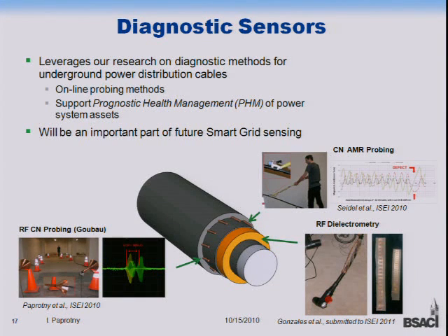The idea is that we can have a sensor that measures the flow of power through the system, but also can tell you when the cable is going to fail, or more importantly, how soon it projects the failure. So if the sensor can measure degradation in the insulator and say, 'it looks like I have maybe 2 years of lifetime left,' that would allow utilities to schedule time where the system can be taken offline and power rerouted, and change the cable out without a disruptive event like a power loss.